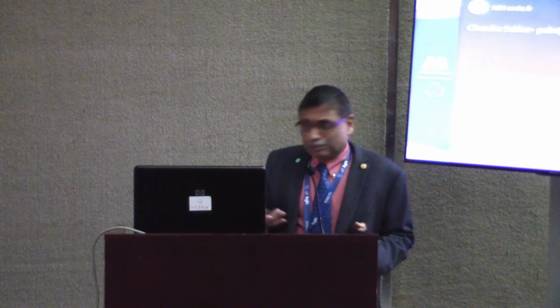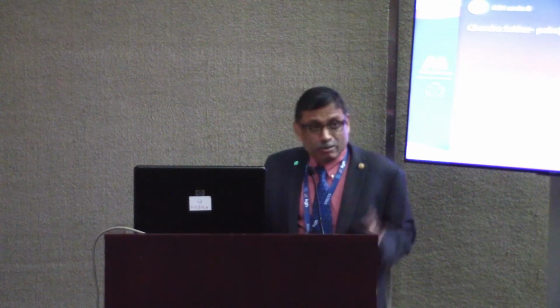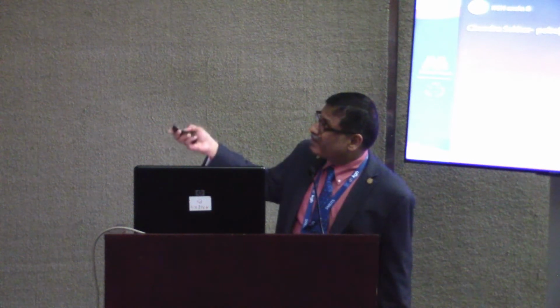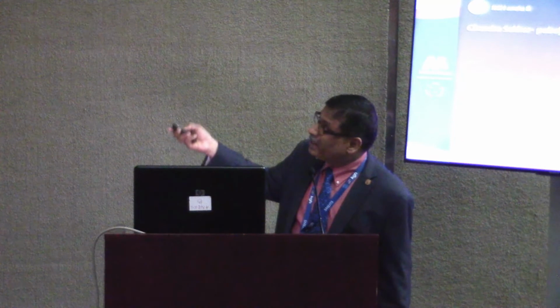Heat pipes, I'm sure most of us here in the audience will be familiar with what a heat pipe is. And again, for us, a heat pipe as a passive energy recovery feature, passive technology, is beneficial if we can implement that in an air handling unit where you want to control both the dew point. Let's not forget that the design consideration has always been, let's address dehumidification needs in an effective, energy efficient manner. So I would not want to just trivialize the need to have good humidity control. We need that. In certain applications, you do need to have a fairly dry condition. So heat pipes really help in that sense. Let's see how it works. We have a cooling coil that's in operation, and we just wrap a heat pipe around the cooling coil. So this is your evaporator section, this is the condenser section. So pre-cooling section and pre-reheating section.